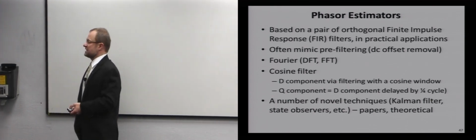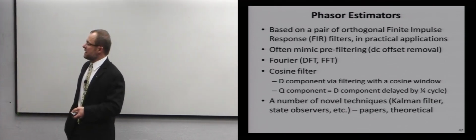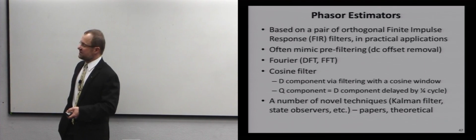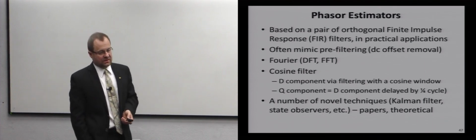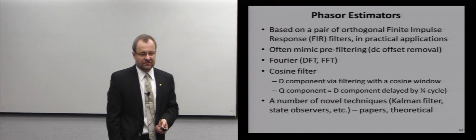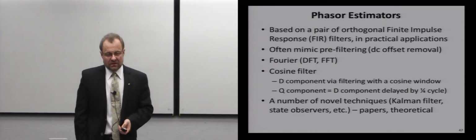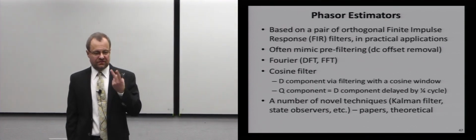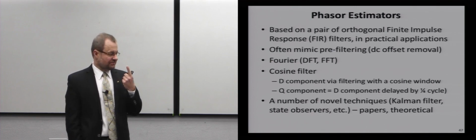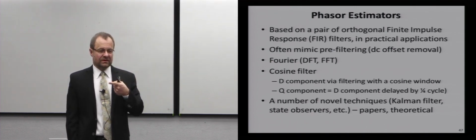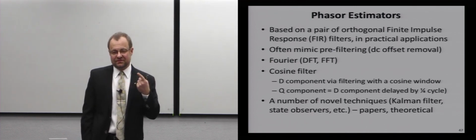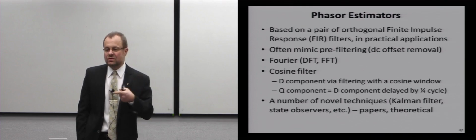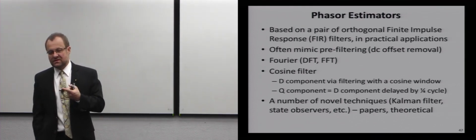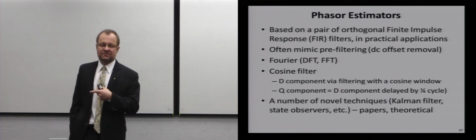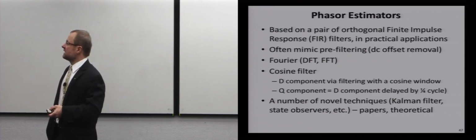We use a cosine filter, which was a very clever thing in early days of relays because it allows you to save a lot of horsepower. Because actually you don't have to have two filters. You could have one filter and the other component is just the first one delayed by a quarter of a cycle. So to get the orthogonal component, you could do it via delay without calculating stuff.